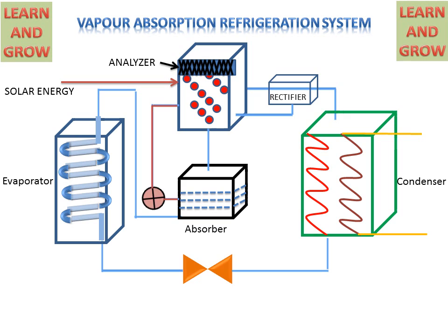In the Generator, Ammonia vapor and some water vapor are formed. Then in the Analyzer, the water vapor are sent back from the Generator to the Absorber. The remaining vapor then go to the Condenser, but in the way there is a Rectifier, which is a heat exchanger that converts water in the Ammonia vapor into liquid form and sends this water back to the Generator and then to the Absorber. Pure Ammonia vapor then proceeds to the Condenser.